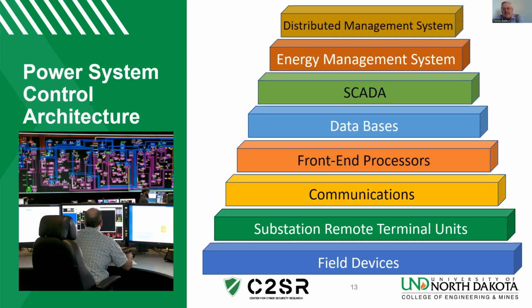Well, non-operational data includes things such as your revenue meters. In other words, the energy that has been bought and sold. Now that heads off to the business offices. Or, shall we say, relay data that shows successful operations. So these usually go to the post-mortems that the engineering teams in the planning department will use to make adjustments to relay settings, and looking at load levels for expansion of feeder sizes and transformer sizes.